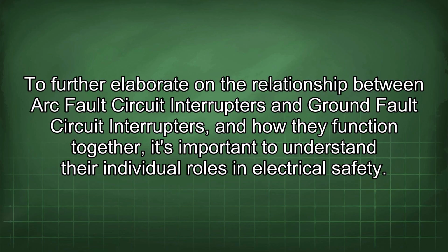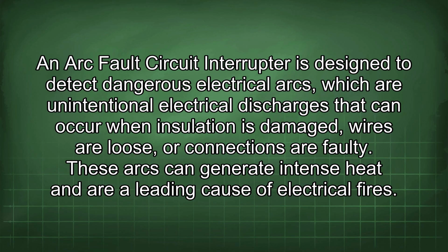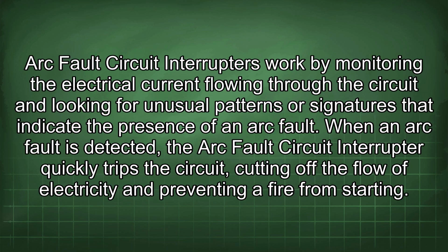To further elaborate on the relationship between arc fault circuit interrupters and ground fault circuit interrupters, and how they function together, it's important to understand their individual roles in electrical safety. An arc fault circuit interrupter is designed to detect dangerous electrical arcs, which are unintentional electrical discharges that can occur when insulation is damaged, wires are loose, or connections are faulty. These arcs can generate intense heat and are a leading cause of electrical fires. Arc fault circuit interrupters work by monitoring the electrical current flowing through the circuit and looking for unusual patterns or signatures that indicate the presence of an arc fault. When an arc fault is detected, the arc fault circuit interrupter quickly trips the circuit, cutting off the flow of electricity and preventing a fire from starting.